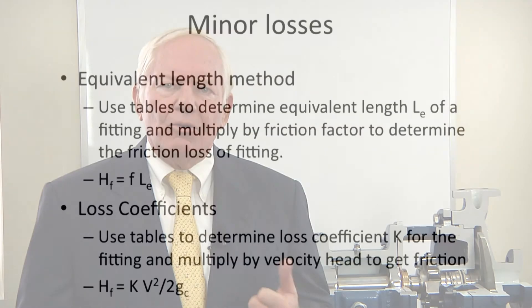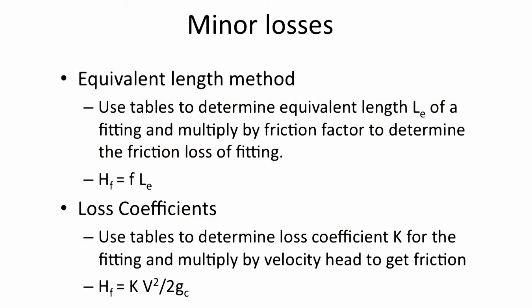There are two popular methods for determining minor losses. One is using equivalent lengths. The other is using velocity heads and loss coefficients. For equivalent lengths, we use published tables to find the equivalent length of the fitting as if it were a straight piece of pipe. These equivalent lengths are then added to the straight pipe length and then used with the friction factor to find the total friction loss. The other method is to determine the velocity head of the fluid, that's v squared over 2g sub c, and then multiply it by the published constant k for the particular fitting.